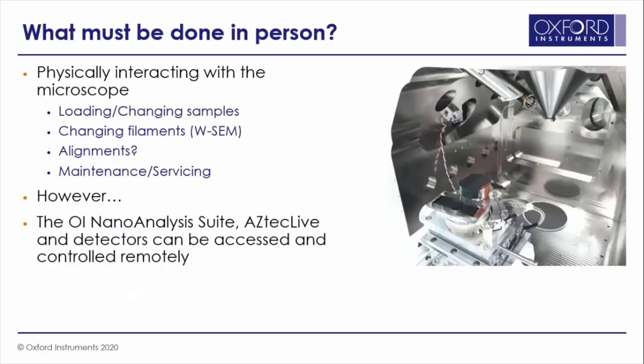There are a few tasks that need to be done in person when running analyses on an electron microscope. The most common and routine of these is changing samples, although there are others such as changing filaments on tungsten SEMs, performing some alignments on some particular models, and maintenance and service visits. Thankfully, in terms of the EDS system, with the advent of the current generation of liquid nitrogen-free detectors, it's no longer necessary to top up coolant on a daily basis. In fact, after the initial installation, it's possible to control all aspects of the analytical systems — EDS, EBSD and WDS — remotely.